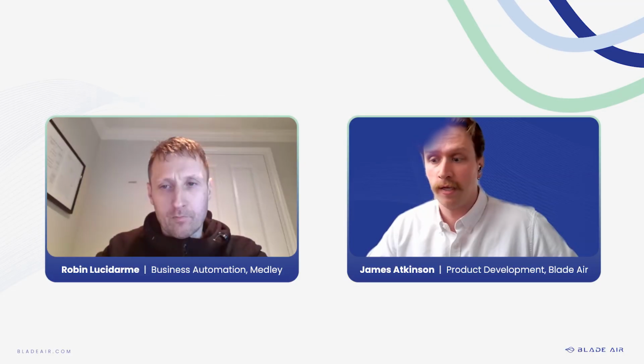Do you have any certification? Yeah, so we are tested with ASHRAE 52.2, Appendix J, MERV 13A tested. I will say one caveat there. The MERV testing is really first pass efficiency is what they are weighted towards. So you get one cycle, they dump some dust in the air, whatever comes out, that's what your performance is.